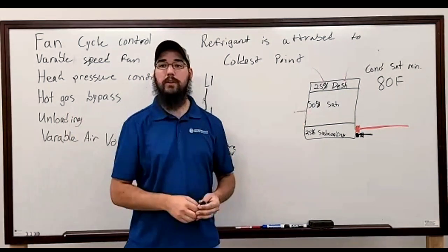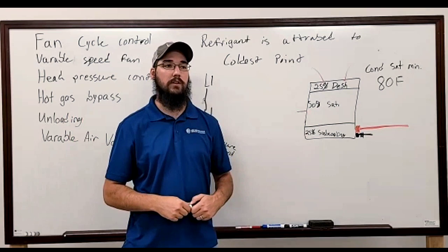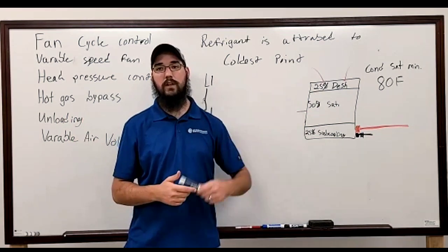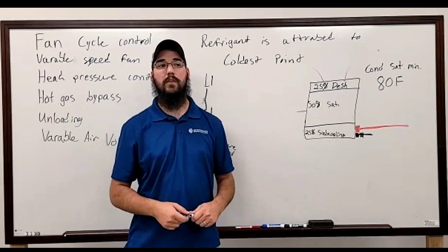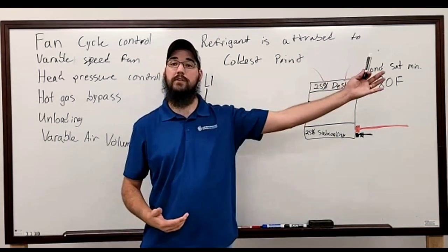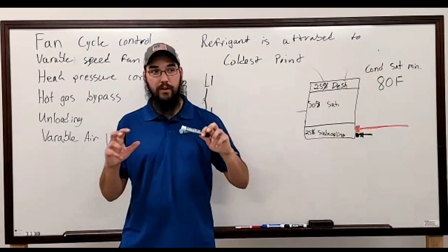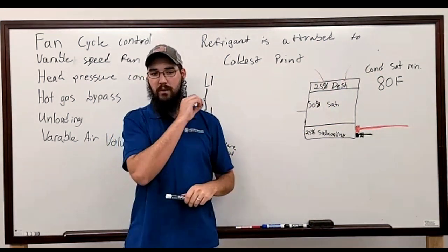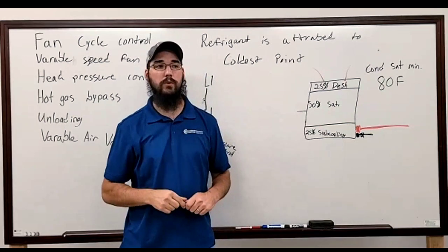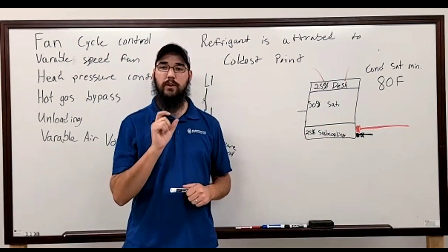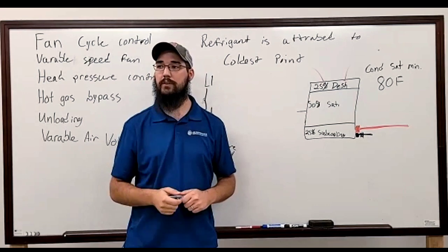Most of the time, honestly, they have no idea what orifice is in there. Their specifications they look back at aren't that specific. We have to know that in the field. Now, they can guess, they can go look at one that's on the shelf, they can do things to kind of figure it out. But that doesn't mean that's what was actually installed on that coil. Do you really want to know what that stamped orifice number is?